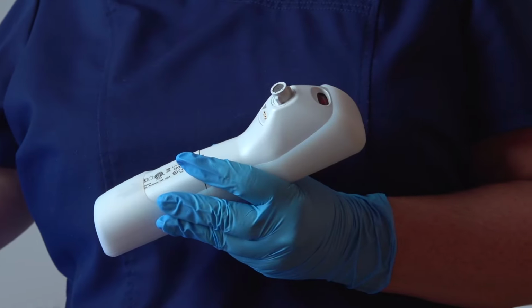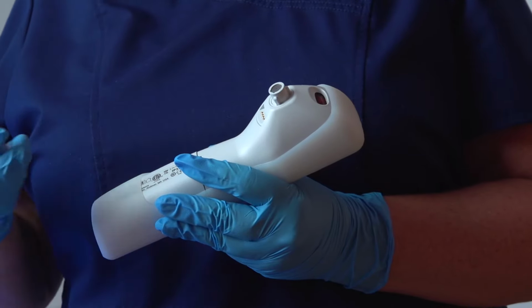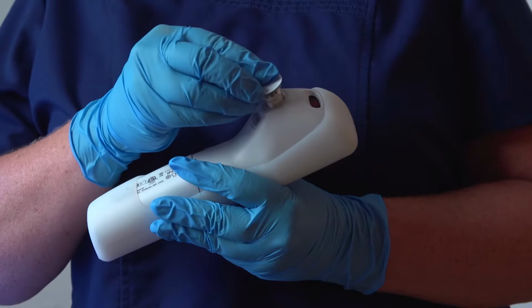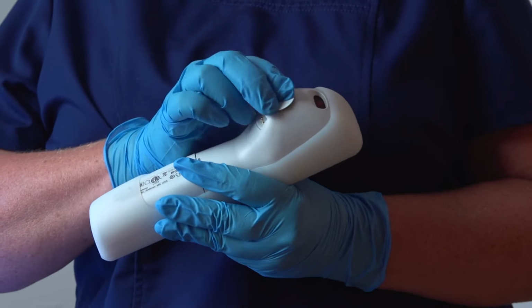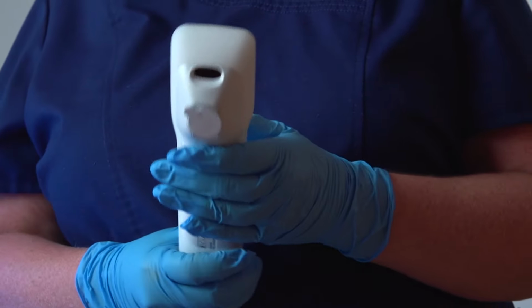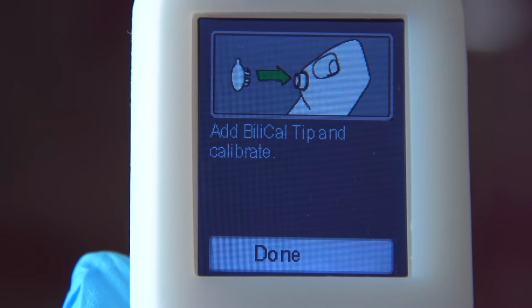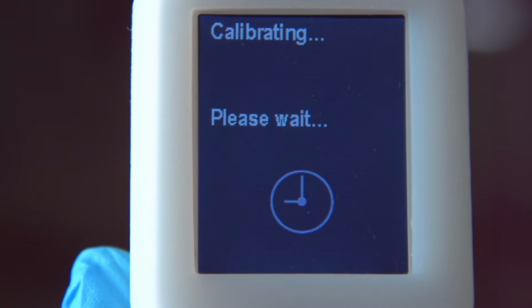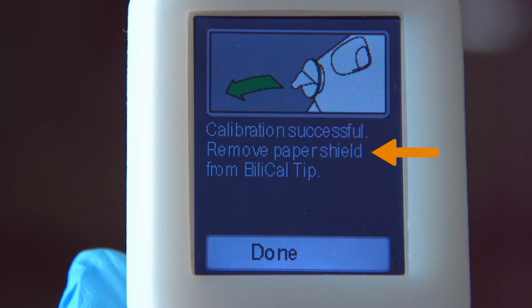Now we need to attach a new BiliCal tip to the handheld unit. Press it onto the unit until you hear a click, which confirms proper seating. Select Done to begin calibration. When finished, the unit beeps and displays this message.